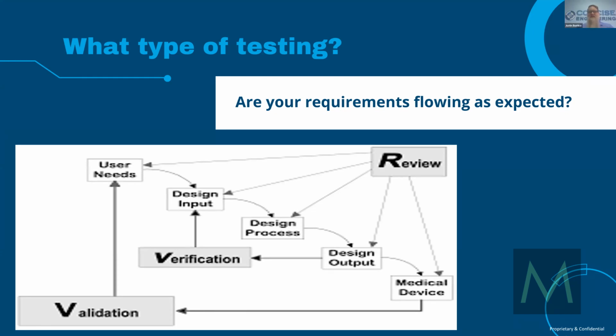So I just wanted to put this out there in case people aren't familiar with the process. This is what the FDA produces, one of the original guidance documents that shows you how you do your reviews, your verification, validation. In essence, your requirements are the white boxes in the middle, the flow of your requirements that eventually end up in your traceability matrix. You would have your user needs that distill down into the design inputs that you then need to address by tangible outcomes, and that would be your design outputs. So you go through that design process to get your design outputs, which is going to be all the different evidence, the documentation, the actual parts, some of the inspections out of that, and then you'll have your medical device. And you're supposed to review it at every stage.